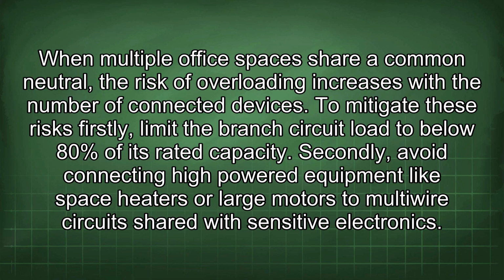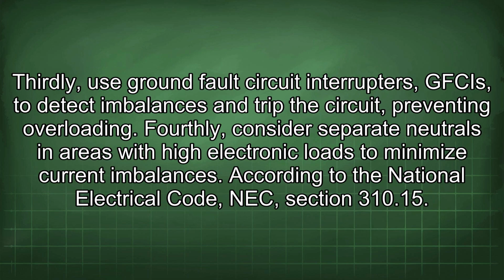To mitigate these risks, firstly, limit the branch circuit load to below 80% of its rated capacity. Secondly, avoid connecting high-powered equipment like space heaters or large motors to multi-wire circuits shared with sensitive electronics. Thirdly, use ground fault circuit interrupters, GFCIs, to detect imbalances and trip the circuit, preventing overloading. Fourthly, consider separate neutrals in areas with high electronic loads to minimize current imbalances.